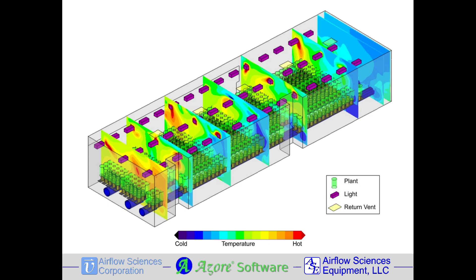The ventilation system for this grow room consisted of three fabric ducts that ran underneath the tables that hold the plants, along with return vents in the ceiling. The model included the heat sources of the lights and outside walls, as well as the added humidity resulting from the plants.